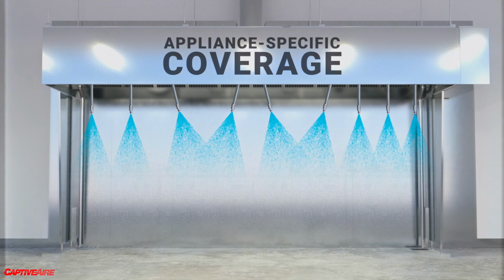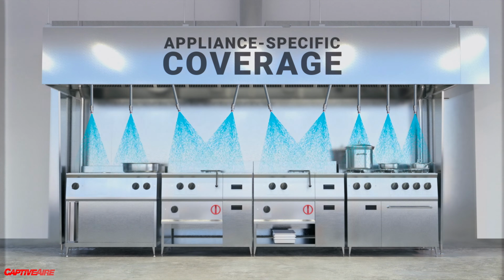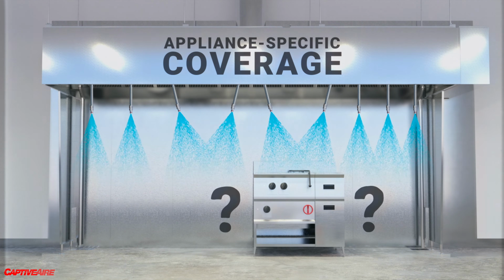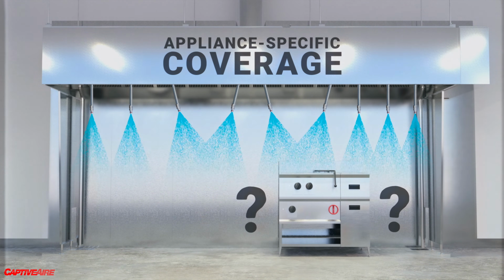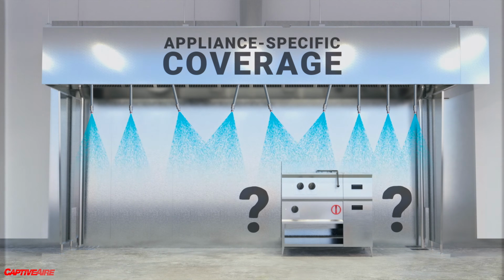Appliance-specific coverage is obsolete as soon as it gets on the job site. The reason is there's a design and then there's actual practice. Design is what we think is going to happen and where the appliance is going to be. Actual practice is where that appliance actually ends up—is it always going to be located where we designed it, or shifted a foot to the left, a foot to the right? We don't know. So the benefit of overlapping coverage is we can negate those variabilities.